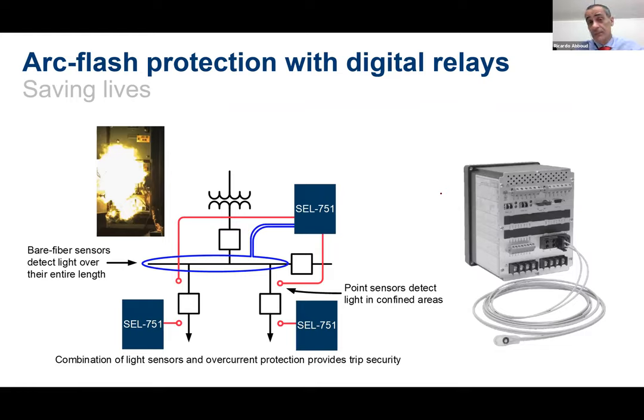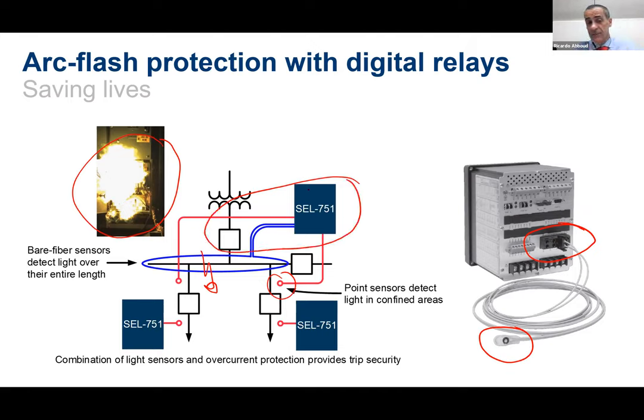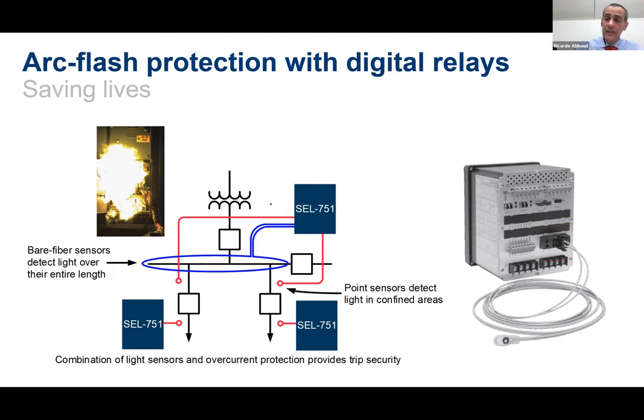In terms of switchgears, we can have relays with the arc flash function also. We have arc flash sensors; depending on the relay, I can have 4 to 8 sensors. We can have different types of sensors: point sensors, or bare fiber, which is a kind of regional sensor. If there is an arc flash fault in the bus, the sensors will sense the light, and the relay installed in the main breaker will receive that information and also measure the current that is flowing. So I can do a combination of light and current, and this relay can trip really fast.